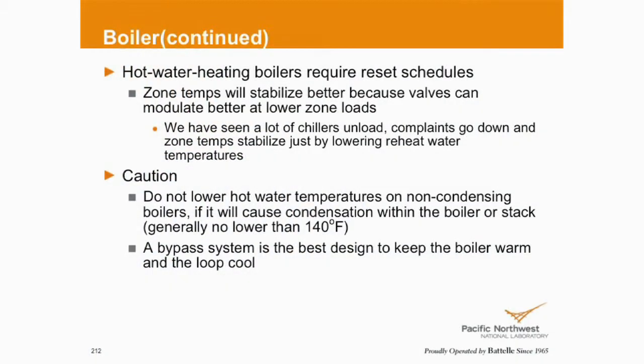So again, related to that, if I'm circulating hot water and I don't have to circulate 180, if I can circulate 120, 140, especially this time of year, I can still satisfy my heating requirements, but do it in a way that's more stable. If I'm circulating 180 degree water, that valve cracks open, boom, fill up the coil. Now I'm discharging who knows what, in excess of 100, 120, and that temperature quickly raises the space, and then all of a sudden it's responding. I'm closing back off, so I can see the cyclical action.